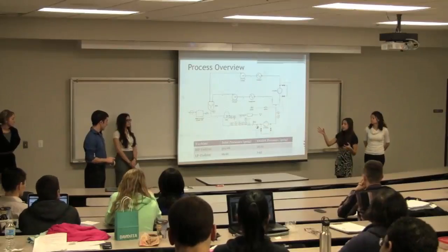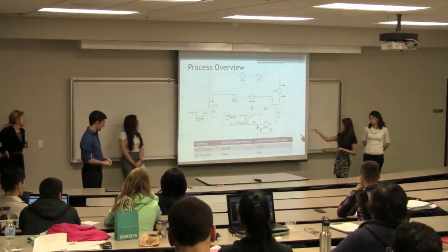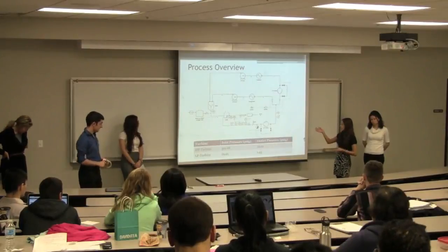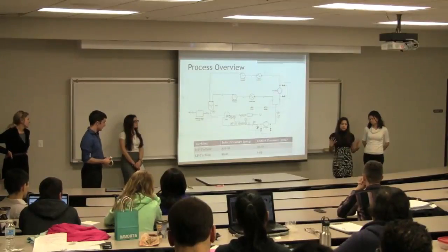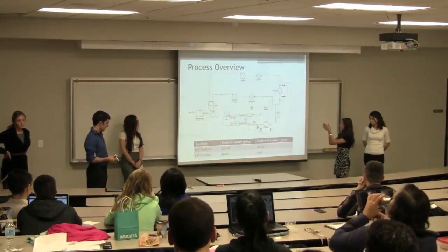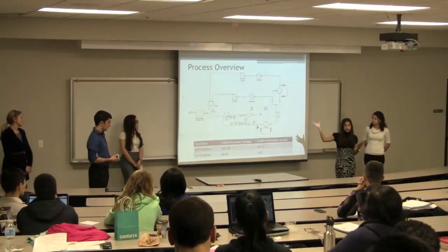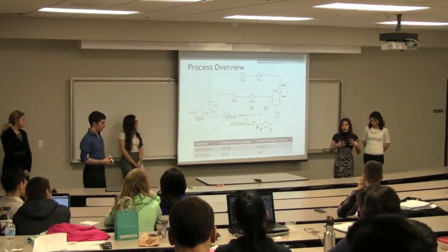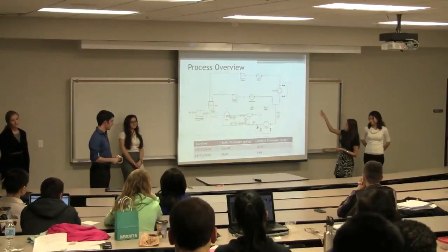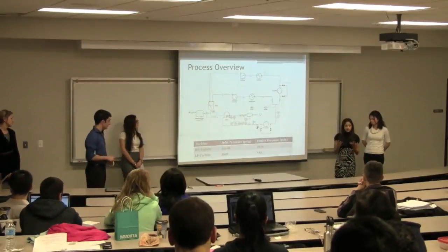Water is heated in the boiler and steam is produced. The steam then travels into the high pressure turbine, where the inlet is about 320 psig and it comes out at 30 psig. The turbine produces electricity from the steam. The rest of the steam is sent to our energy clientele, buildings that need heat. The remaining steam goes into the low pressure turbine, which enters at about 30 psig and drops to about atmospheric pressure.